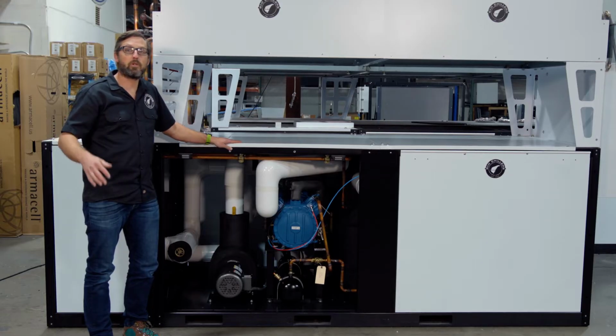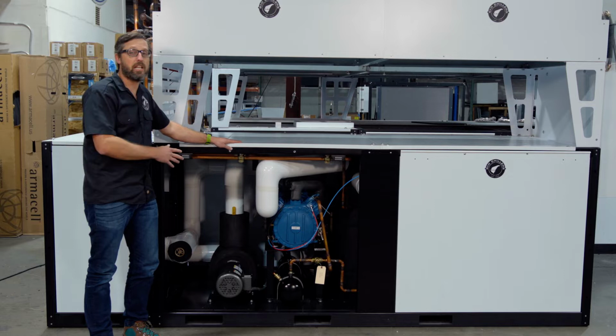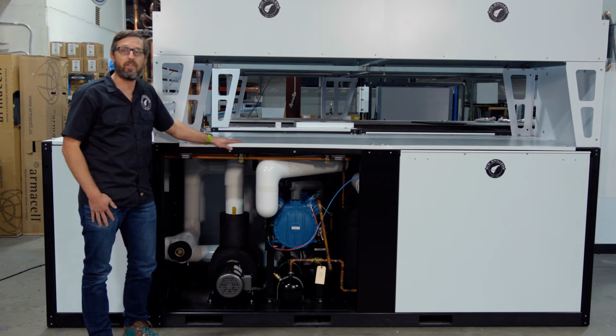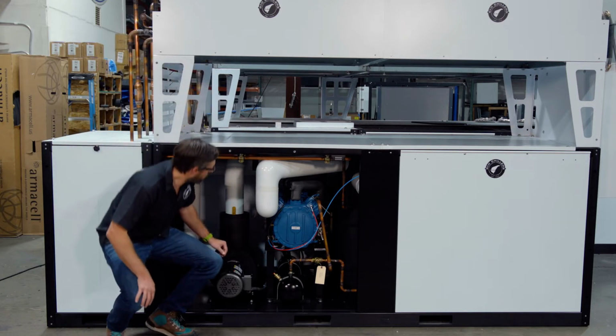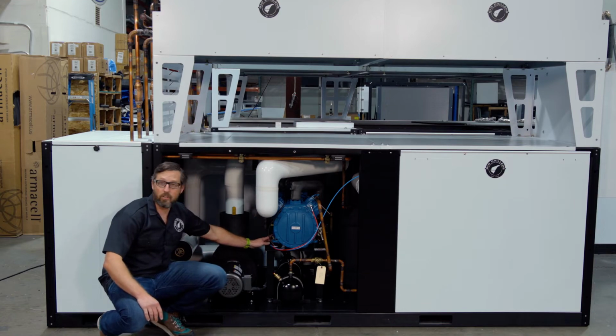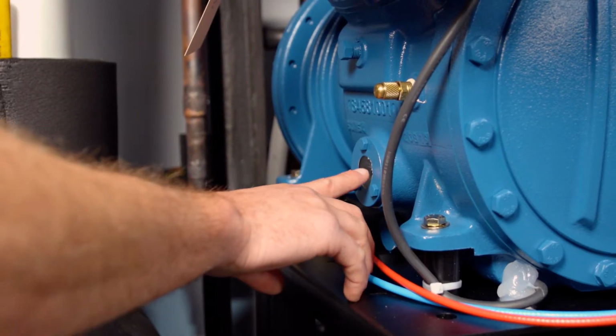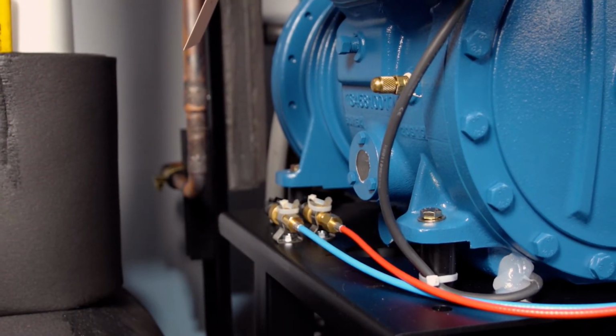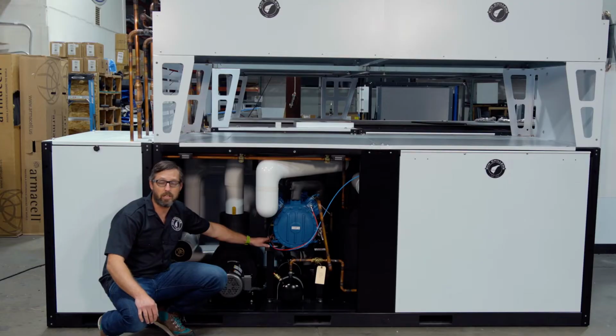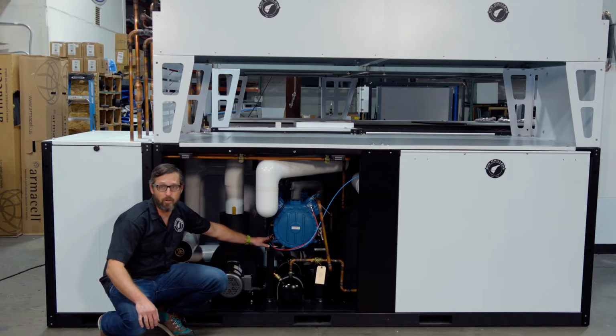So after 4 hours with power to the system, we're going to come to each one of these compressors and check that there's a visible oil level. The sight glass to look at is right here on the side of each compressor, and like I said, you're going to want to check that you can see oil in each one of those sight glasses. If you can't, you need to wait longer. If you can, then we can move on to the next step.